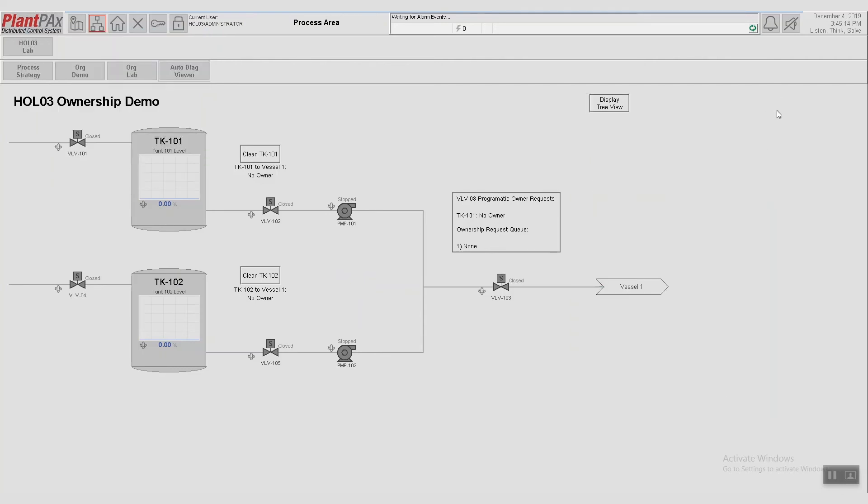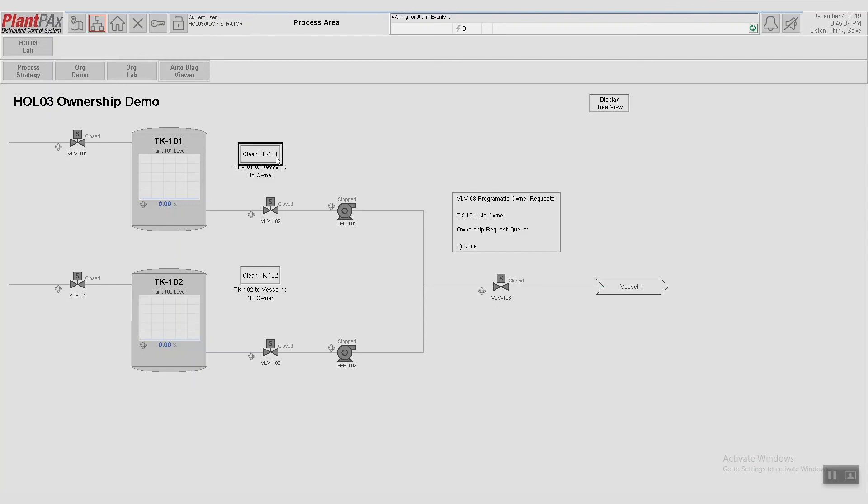The other value add of this new feature is that it allows you to better manage shared equipment. So looking at this HMI screen, you can see that both Tank 101 and Tank 102 want to use this distribution valve, valve 103. So if we're executing sequences in our plant's operation, we want to make sure that both aren't trying to use that valve at the same time. So if I start up a clean Tank 101 operation, it starts up a cleaning operation and we can see that this shared valve is owned by Tank 101.